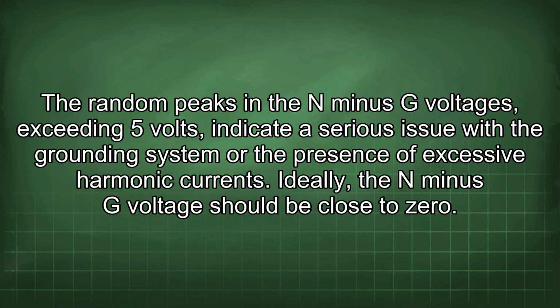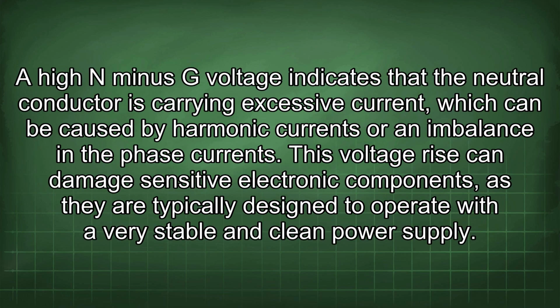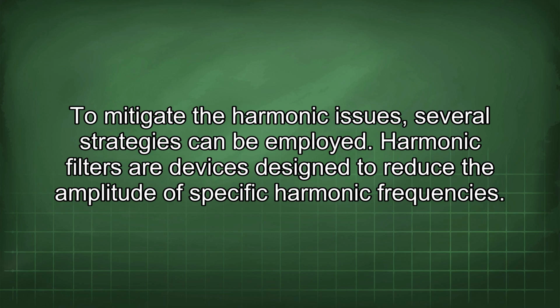Ideally, the N-G voltage should be close to zero. A high N-G voltage indicates that the neutral conductor is carrying excessive current, which can be caused by harmonic currents or an imbalance in the phase currents. This voltage rise can damage sensitive electronic components, as they are typically designed to operate with a very stable and clean power supply. To mitigate the harmonic issues, several strategies can be employed.